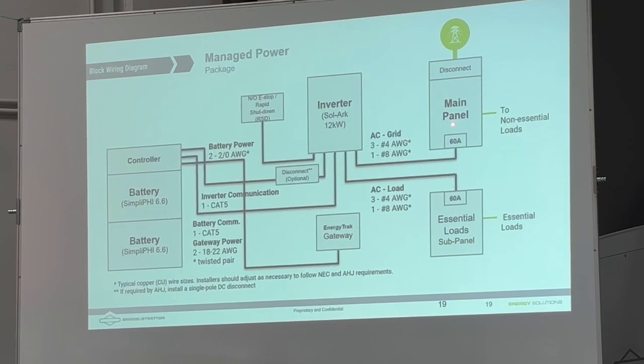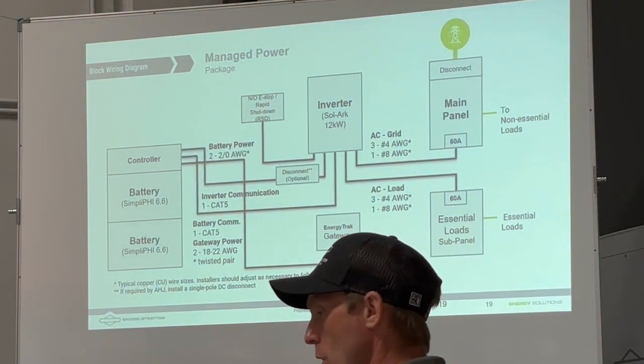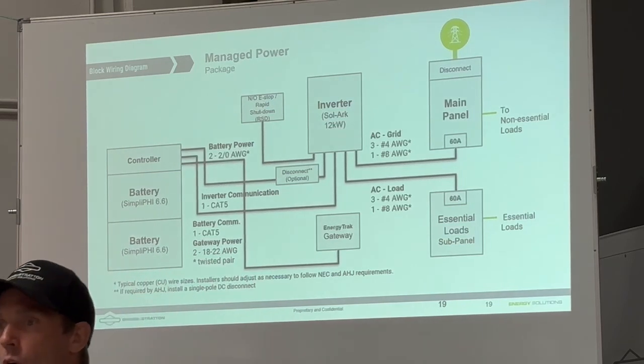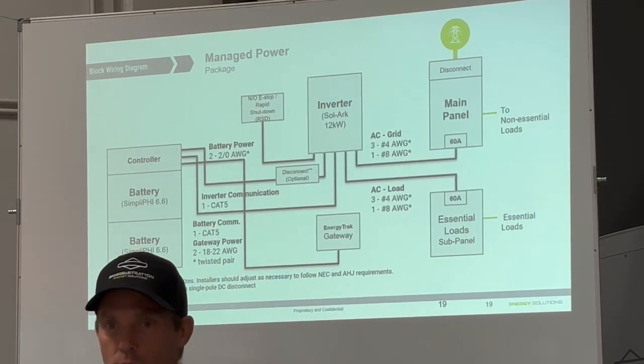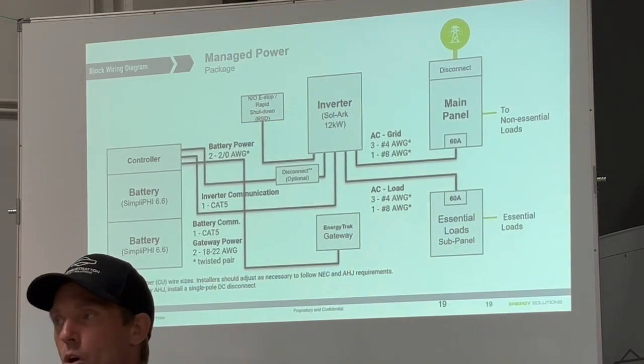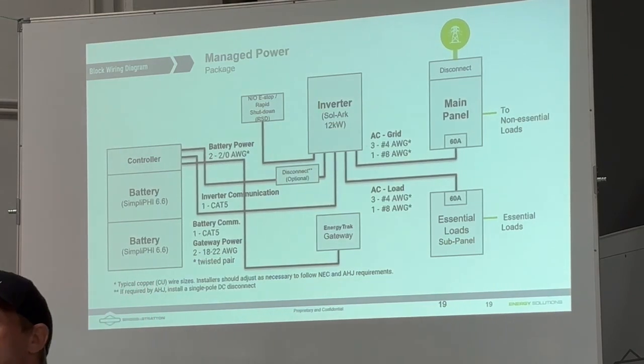But you essentially have 63 amps of pass-through in the 12K and the 8K inverters. It's the same limitation with the pass-through there. I also point out here the 120% rule, so who knows where the 120% rule is? Okay, so we don't want to overload our bus bars, right? So if you've got a 100 amp bus bar, you can't have more than 20 amps backfeeding that bus bar because you can only go 20% over the ratings of the bus bar.